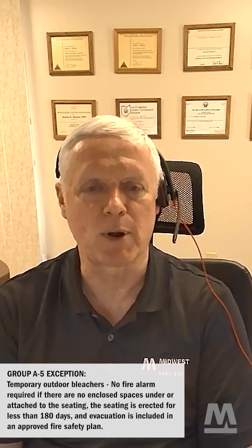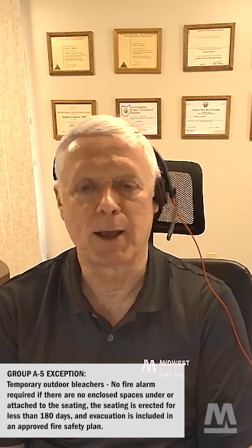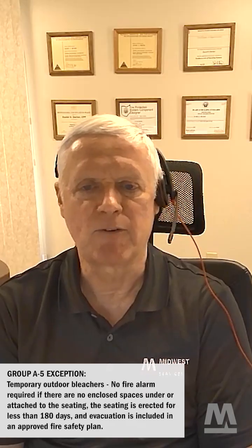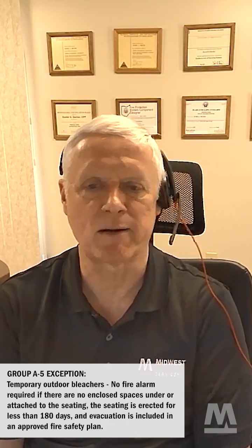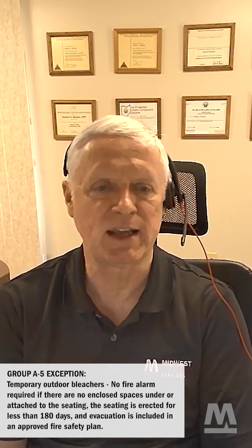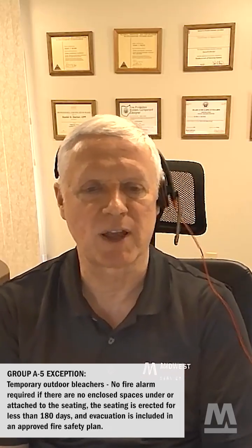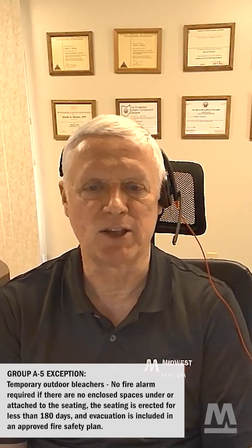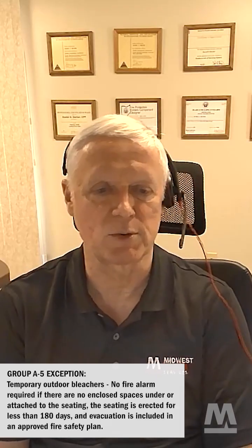If you've got temporary outdoor bleachers, no fire alarm is required if there's no enclosed spaces that are under or attached to the seating, or the seating is erected for less than 180 days, and you've got an approved fire safety plan that deals with evacuation.